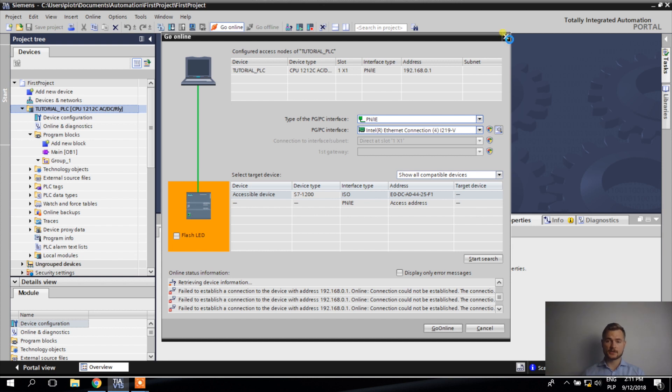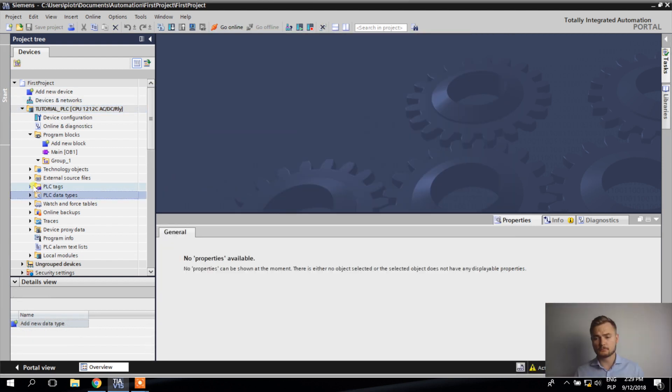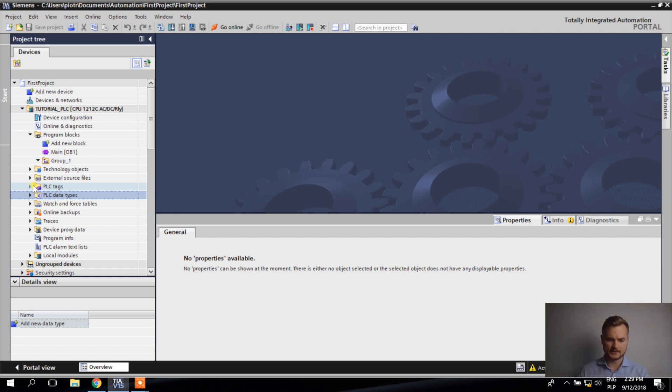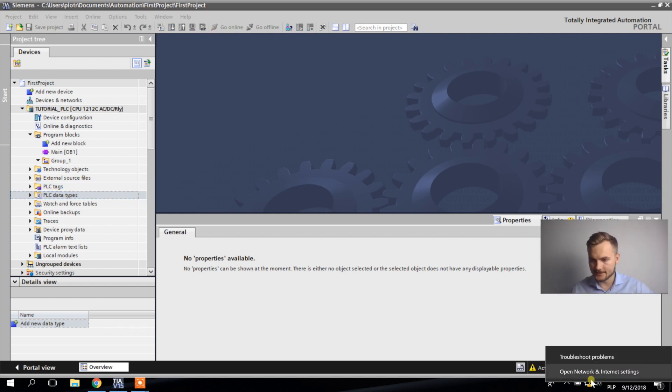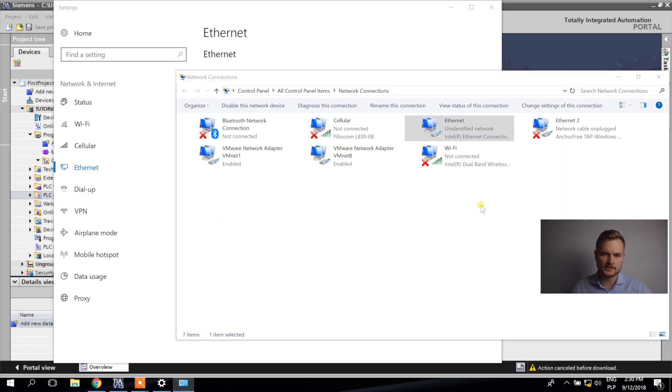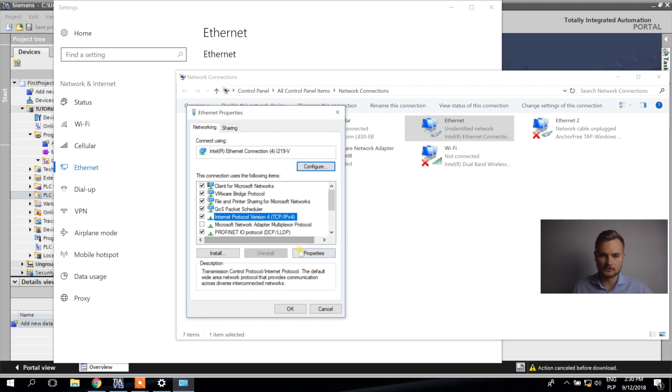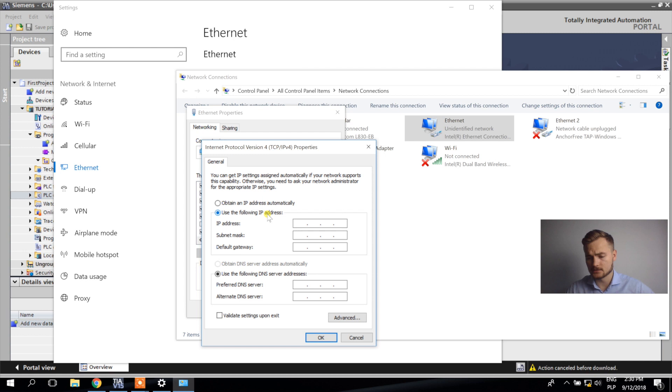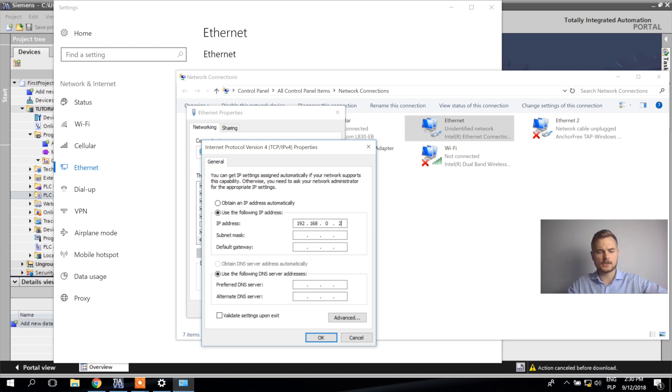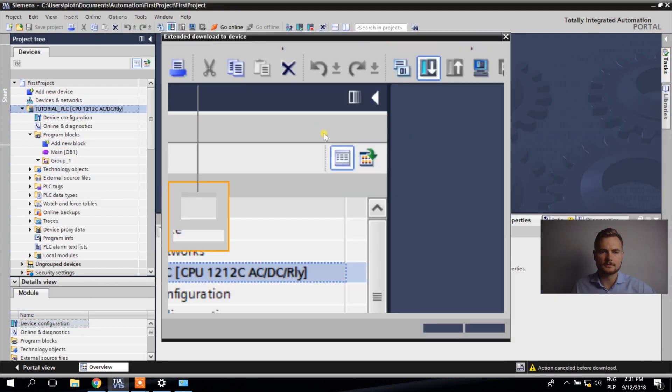All right, the connection failed because the online target could not be reached. The address doesn't match, I guess this is the reason. There are a few possibilities why it could have happened, and my first guess would be either it's a difference in firmware or the networks are different. So I'm going to go to the network settings and see properties here. Internet Protocol version 4, properties. For the PLC I'm using the network 192.168.0.1, so I'm going to use a similar one, 0.2, with the subnet mask like this.